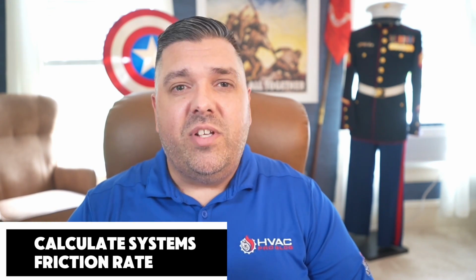Step 1, calculate your system's friction rate. Let's start with the foundation, and this is where most contractors go wrong. You can't evaluate existing ducts without knowing what your new system demands. Here's the reality. When you're moving from an old 80% furnace to a new 95% high efficient unit, everything changes. That new furnace needs significantly more airflow because of its lower temperature rise. I've seen contractors install beautiful new equipment only to discover the existing ducts can't deliver the required CFM.